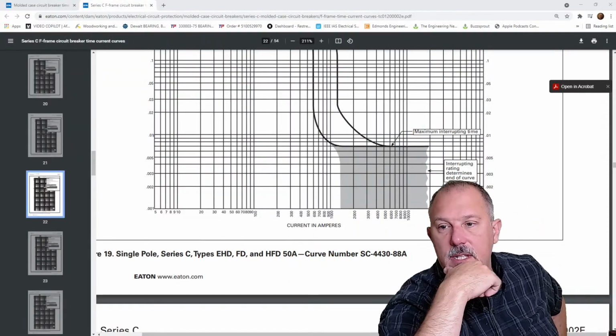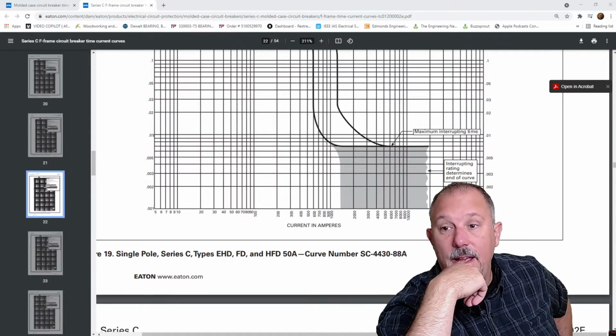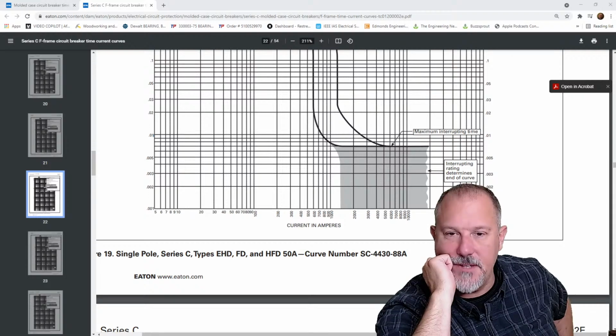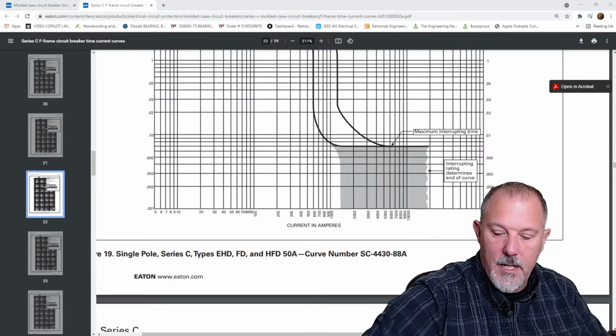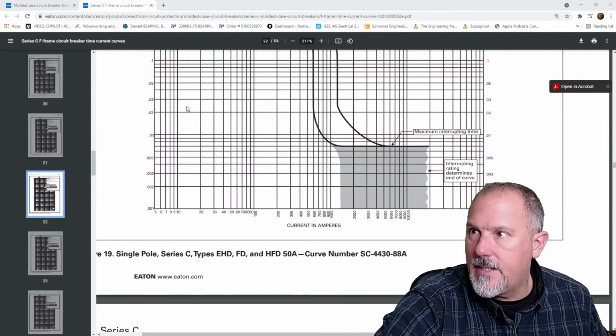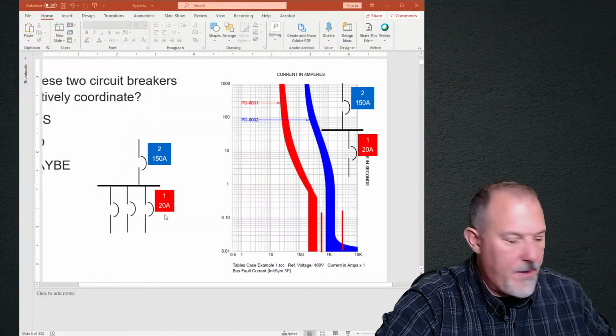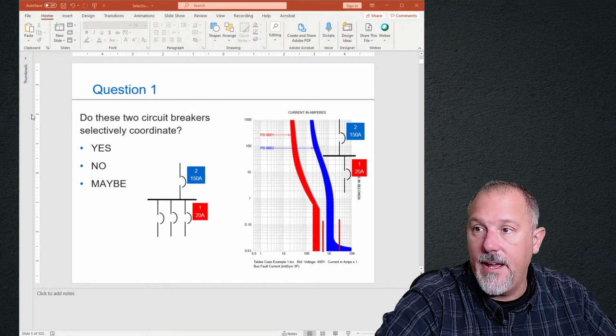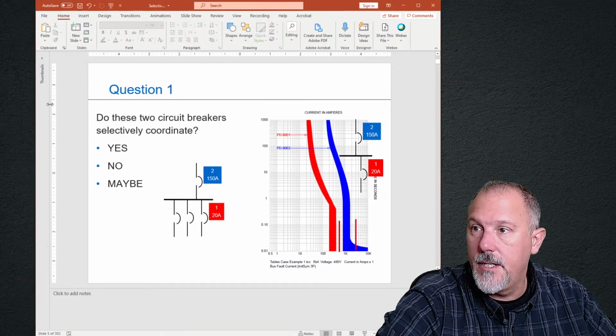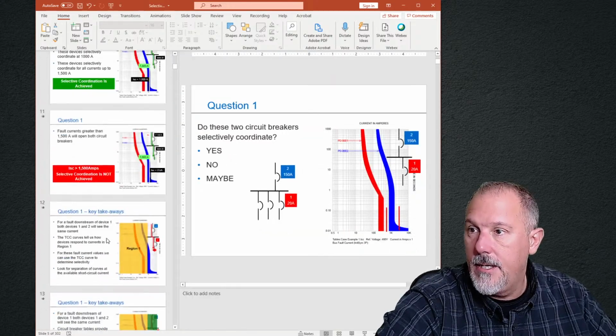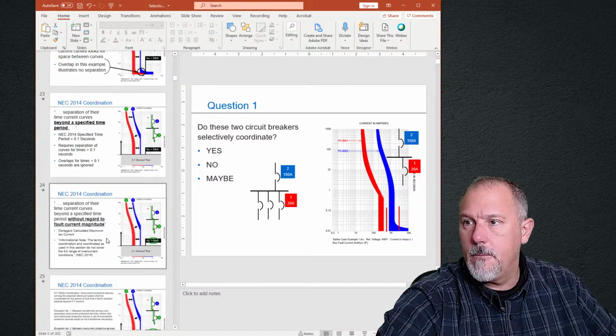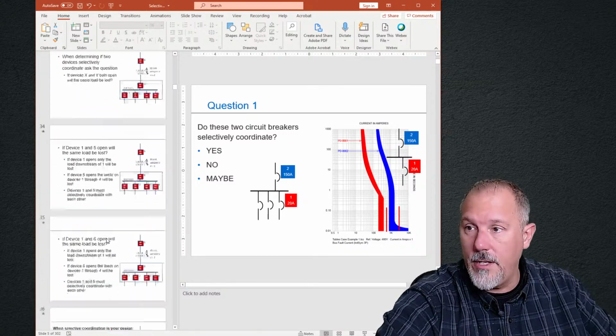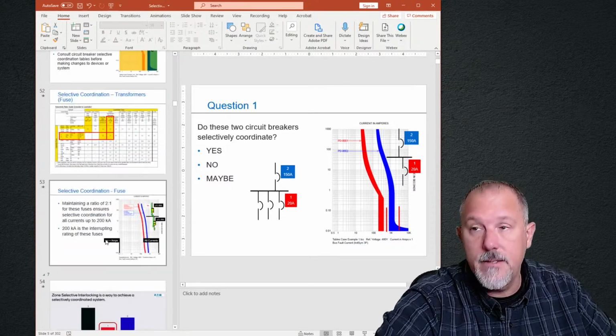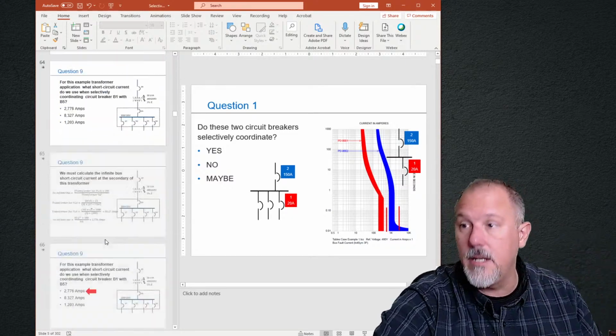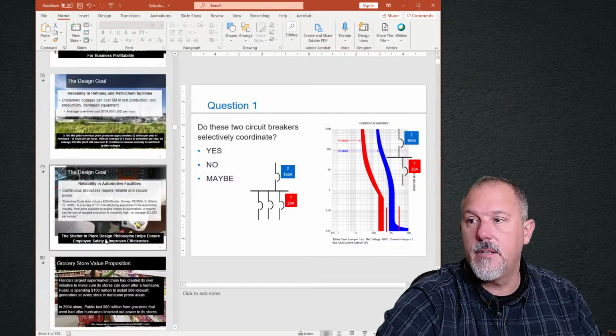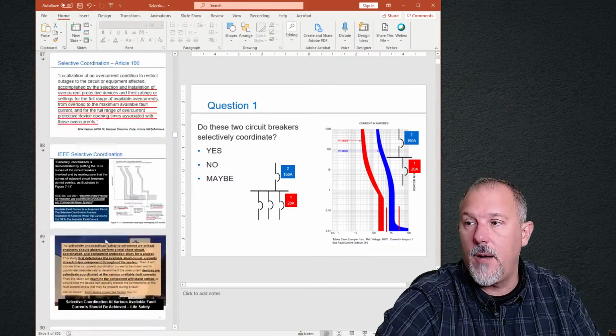When does a system have to be selectively coordinated other than for emergency systems? Healthcare. I knew, David, you were going to go there. Healthcare does not selectively coordinate. So let's take a look at what does. I think I have the sections in the code that require selective coordination. I think I have it in here. 700 does, 701, Article 701, 708, right? So 701 is your legally required standby systems. 708 is your critical operations power systems.